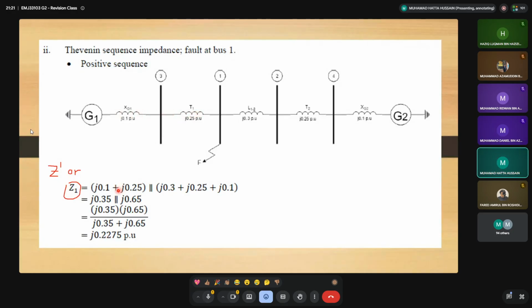So this J0.1 you need to add together with the reactance of transformer 1 here. But this one is actually in parallel because the fault occurs at bus 1, meaning there's a node there. So in parallel we have J0.3 plus J0.25 plus J0.1, which becomes in series, giving us J0.65.